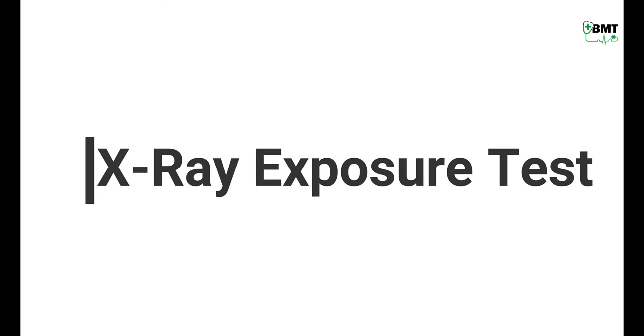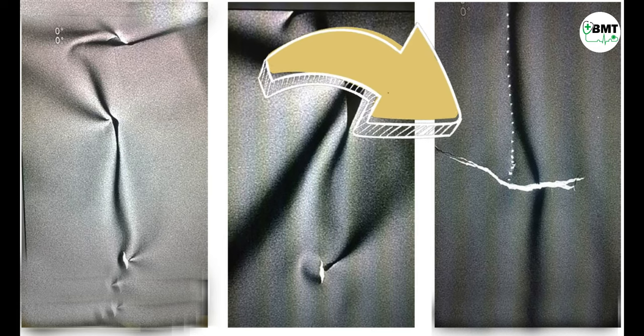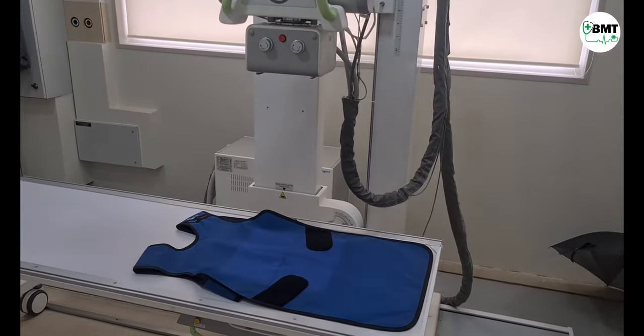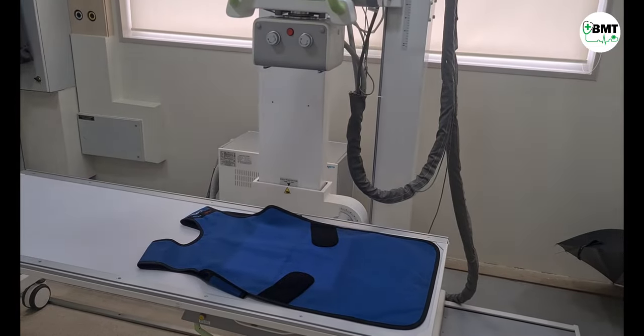How to do an x-ray exposure lead apron test if found visually defective? If any defective part is found in visual inspection, place that suspected portion of the apron below the x-ray exposure with higher kVp and lower mA settings.